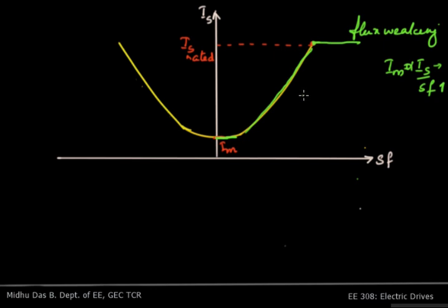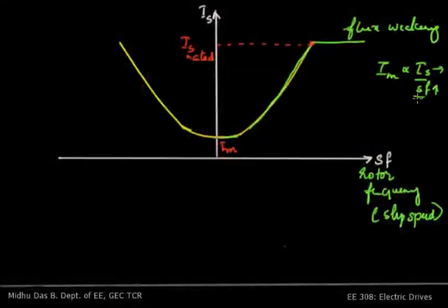Alright. The motor will draw a constant current for a given slip speed to maintain this Im constant, and therefore it develops a constant torque at all the frequencies. So even if frequency is changed to control the speed, the slip will get adjusted and Is by SF will be maintained constant. Therefore the motor will operate at constant torque mode from 0 to base speed of the motor.